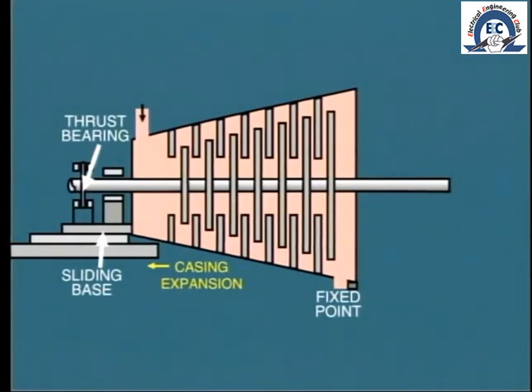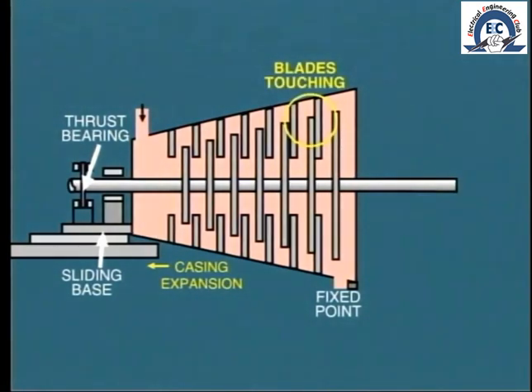It would be convenient if both the rotor and the shell were to expand at the same rate, but in practice this does not happen. The reason is that the rotor is considerably lighter than the shell, and therefore it expands more rapidly. So during the initial loading of a cold machine, the rotor expands at a greater rate, and we run the risk of the rotating blades coming into contact with the next stage of stationary blades. This differential expansion must be kept within certain limits by restricting the rate of change of load on the machine.